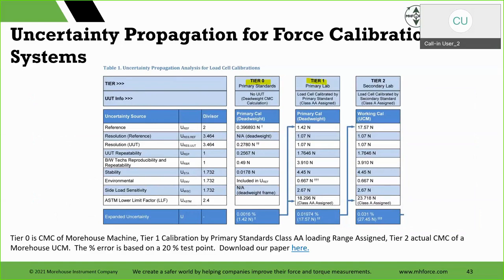And this is what we're showing. This is from 20% of the cell's capacity. So if I have, I like easy round numbers, if I have 100K UCM and 100K ultra precision Morehouse ultra precision load cell, and I'm doing my test, what we're showing here, and we did this in our lab, is that at the 20% force point, we're getting 0.019, so 0.02. At capacity, we were getting numbers like 0.005. But this is our highest uncertainty.